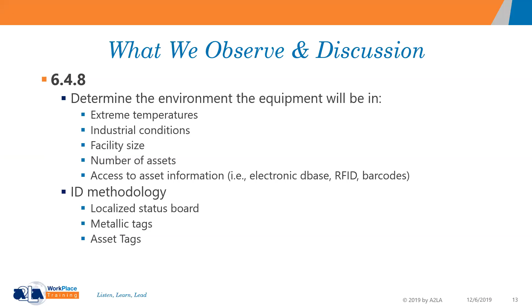As mentioned before, you can ID equipment in any way you can imagine. You can have a localized status board. I went to an aerospace facility machining turbine blading, and they had a status board with all the different IDs on it, with calibration due dates and maintenance due dates, on a board not attached specifically to the assets but traceable by an ID on the asset. You can use metal tags, asset tags, RFIDs. The sky's the limit on what you can do here.